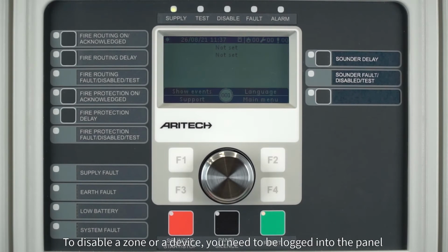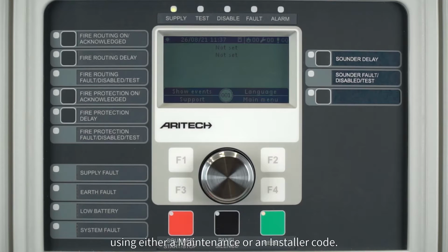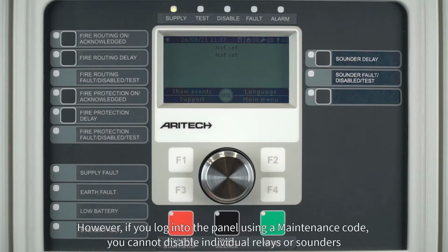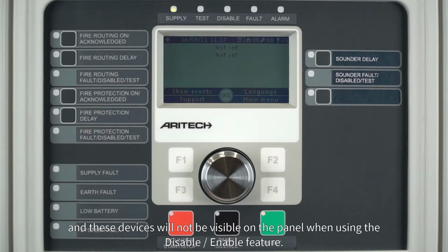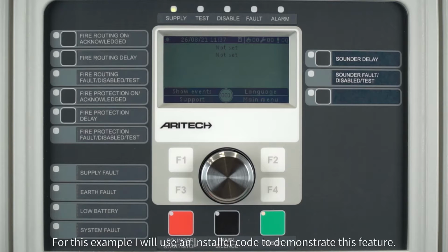To disable a zone or a device, you need to be logged into the panel, using either a maintenance or an installer code. However, if you log into the panel using a maintenance code, you cannot disable individual relays or sounders, and these devices will not be visible on the panel when using the Disable Enable feature. For this example, I will use an installer code to demonstrate this feature.